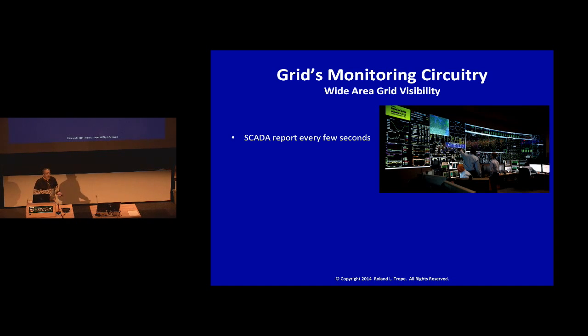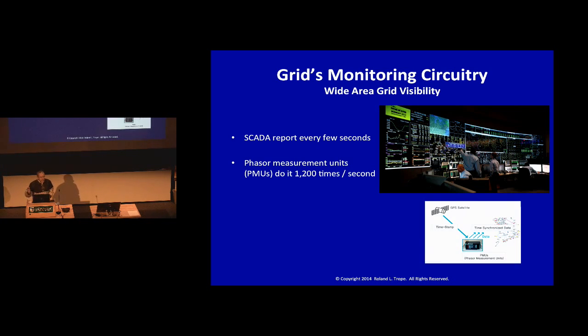That in today's grid isn't fast enough. So increasingly they're using phasor measurement units that do readings 1,200 times per second. That's pretty fast. That gathers the data. It then is put through some algorithms and produces certain measurements to inform people in the control room, this is the status of your system. And it gets time stamps so that we know what was the system doing at this time, and if it has a problem later, we can go back and learn our lessons.